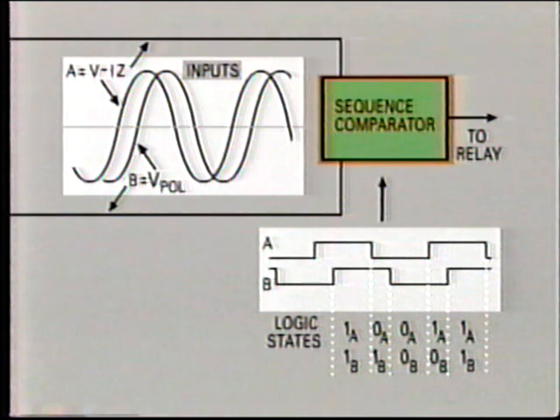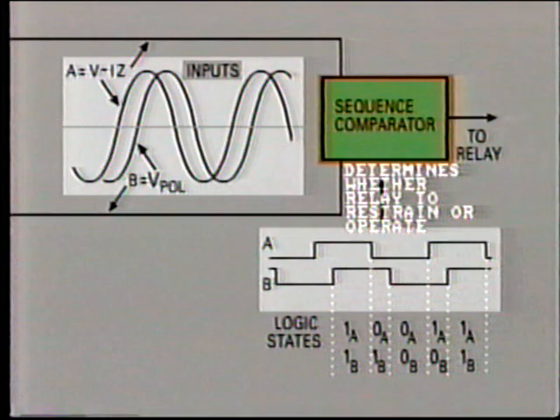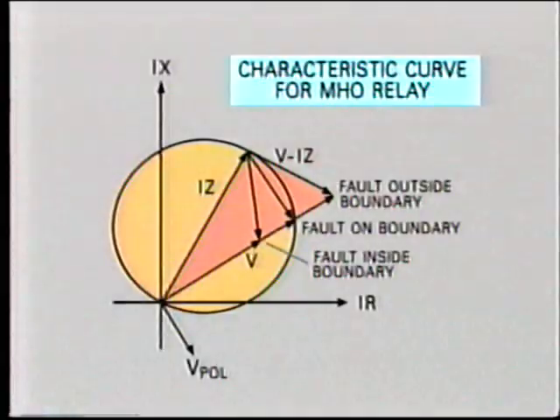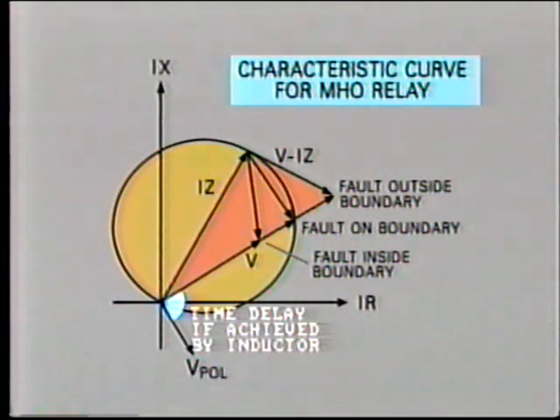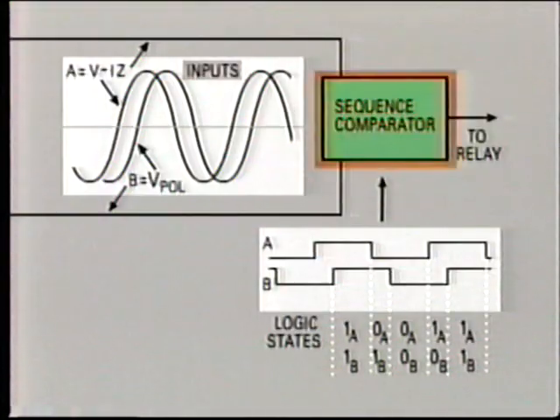The comparator's digital logic circuit examines the sequence of ones and zeros and determines whether the relay must restrain or operate. A precaution is necessary in providing the 90-degree lag to the polarizing voltage. If this were to be achieved by an inductor, the signal would experience time delay. Instead, the phase shift is achieved digitally in the sequence comparator itself. Now remember, we're trying to show a variety of examples here. Your specific protection equipment may have entirely different circuitry.